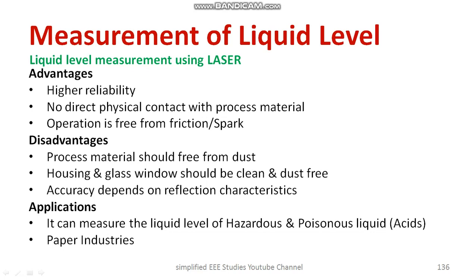What are the advantages? It is a highly reliable method. There is no direct physical contact with the process material, which is a highly advantageous feature, especially for risky fluids — some fluids are totally harmful to health. In such cases, laser technology is ideal for liquid level measurement. The operation is free from friction or spark, there are no moving parts, and efficiency is very high.